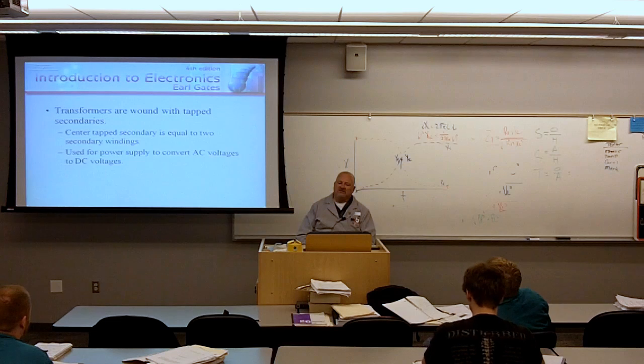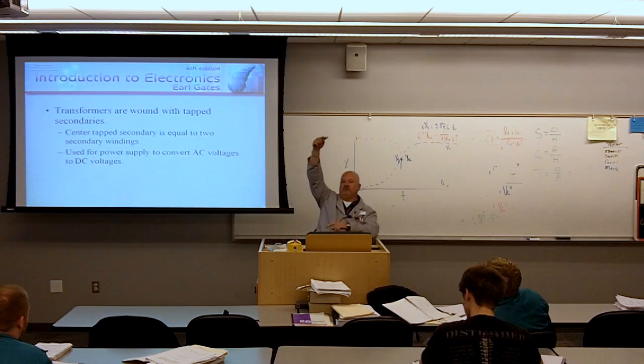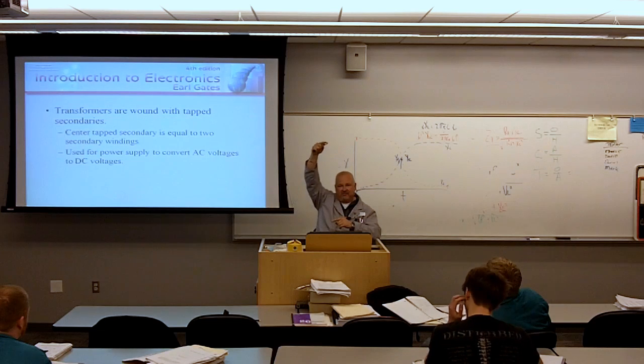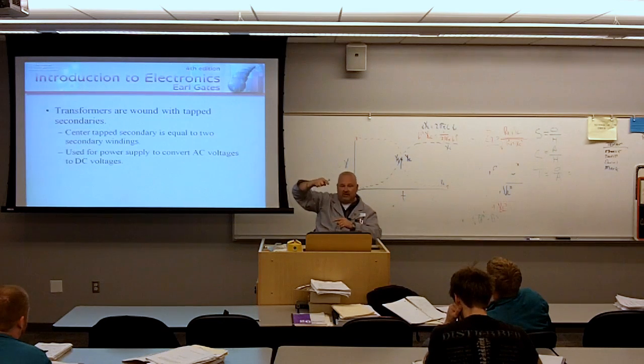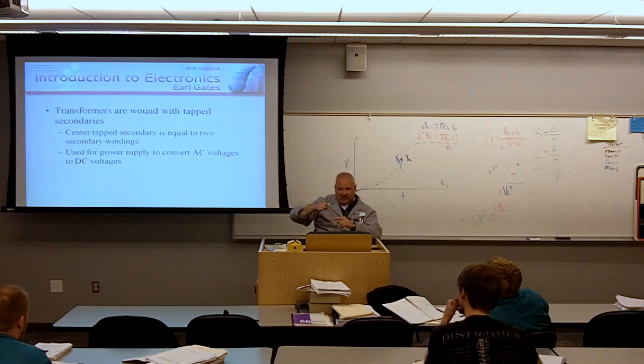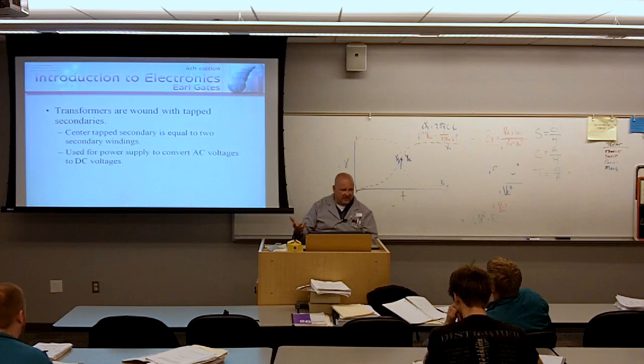Transformers are wound with tapped secondaries, what are called tapped secondaries. A center tap secondary is equal to two secondary windings. Basically what they do is get 100% of the secondary winding, and then put a connection into the center. So you've got 50% of your winding between here and here, and then 50% between here and here. Some transformers have multiple taps, and the reason they did this in the past was so you could create multiple voltages out of your secondary.